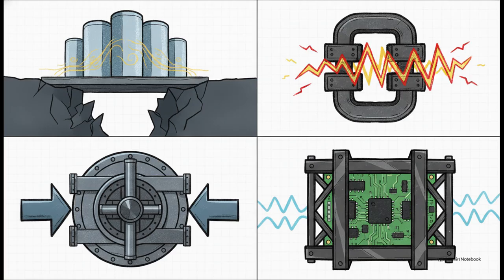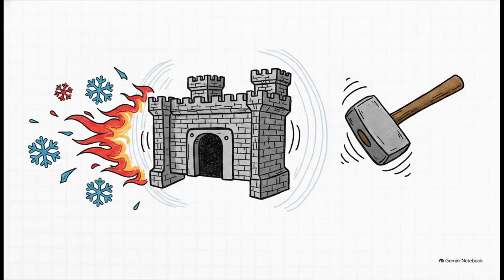Plus, they don't just turn the gate off at 0 volts. They inject a negative 5-volt bias, forcefully slamming the electronic doors shut and locking it. And what about those invisible mechanical earthquakes? They dynamically tune the physical circuit board structure. They add rigid metal reinforcements to guarantee its natural frequency stays far, far away from that 100 to 1000 Hz danger zone. The material science happening here is absolutely fascinating.